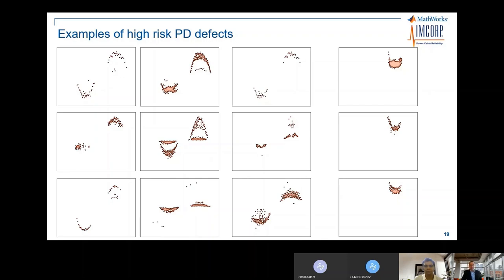Here are examples of electrical tree type defects that the machine found automatically. When looking back into the data, these turned out to be the ones a cable network owner should address first. This information is retained in a database that automatically categorizes and prioritizes risk of partial discharge defects going to failure.